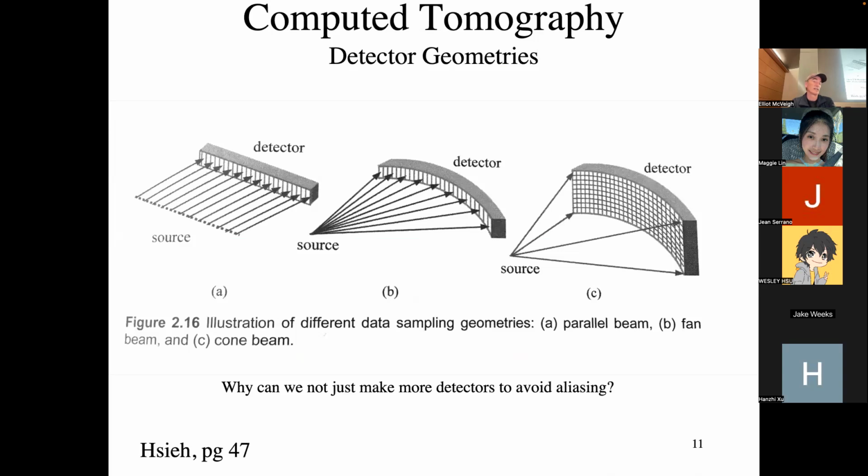For CT, it's pretty simple, right? We build a detector, remember, and if we're going to sample rapidly, this detector is fixed in place, and we have little bins that are each integrated across that bin as one sample, right? So right now, when I look at this, I'm already at a discrete sampling method. I have picked my sampling rate by picking the separation between these bins.